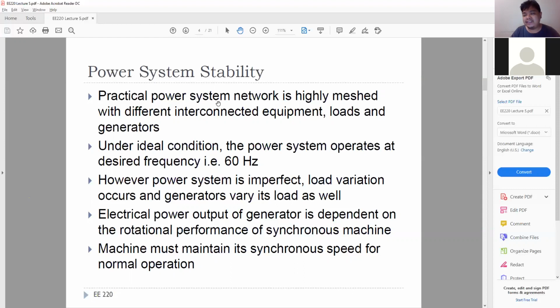So really, what happens is they have a stricter range with different frequency control mechanisms. Particularly, the ones managing our frequency are the frequency control ancillary services. Now, the frequency control ancillary services, currently, particularly what's called regulation, maintains the frequency around 59.85 to 60.15.